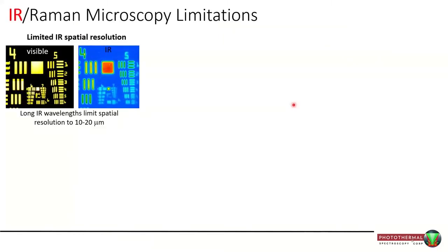Infrared spectroscopy and microscopy is a fairly mature technique and as such it's reached its limits. Its most fundamental limit is spatial resolution — since we're dealing with infrared wavelengths, our spatial resolution cannot be as good as in the visible. You can see that clearly: the visible targets are crisp and sharp, but in the infrared things blur out. Most infrared microscopes get resolutions in the order of 10 to 20 microns.